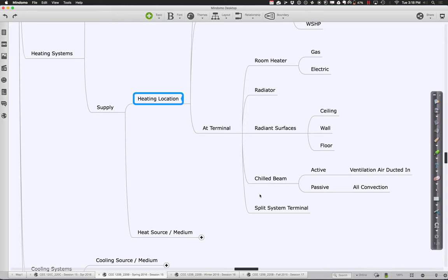We don't do that as much anymore, although not up in the ceilings. If we're doing radiation systems, we'll typically run hot water to the floor or something like that. That's what we do in this building. We run the hot water to the floor to bring it up to the basic temperature. There are also these chilled beams, those are the ones right above us.